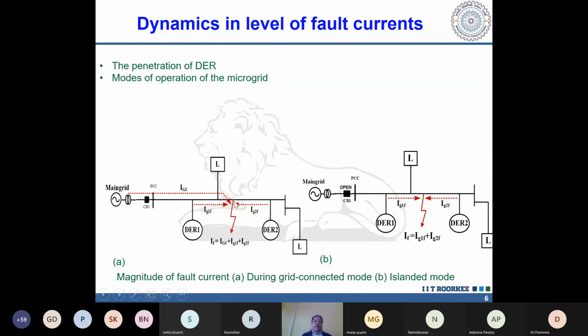As I said, when a fault is incepted in any feeder, the main grid's PCC bus has higher voltage compared to the fault point voltage, because at the point where the fault is incepted, the voltage dips. So this voltage difference between VPCC and V-fault creates a gap, and due to that, current is supplied by the main grid. Similarly, the voltage available at the DER1 terminal is also higher than the fault point voltage, and similarly for DER2.